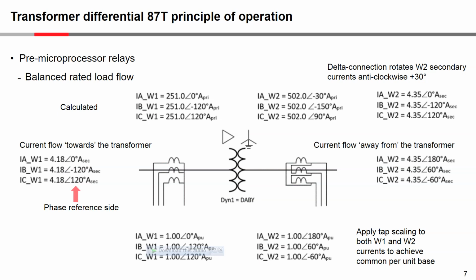And then if we apply the tap, okay, I just made it a perfect tap on each side, that would give you 1 per unit. You can see that the current flowing in on the winding 1 side, if you sum that with the current flowing out on the winding 2 side, the differential current in each phase would sum to 0.